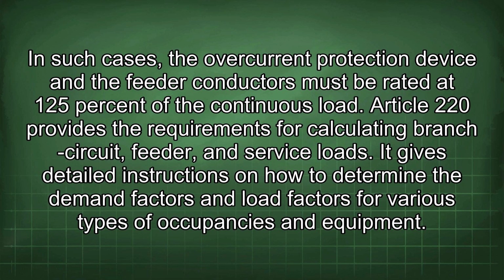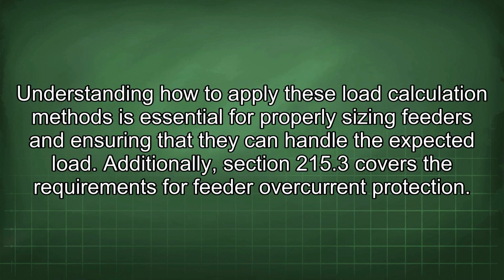Article 220 provides the requirements for calculating branch circuit, feeder, and service loads. It gives detailed instructions on how to determine the demand factors and load factors for various types of occupancies and equipment. Understanding how to apply these load calculation methods is essential for properly sizing feeders and ensuring that they can handle the expected load. Additionally, Section 215.3 covers the requirements for feeder overcurrent protection.